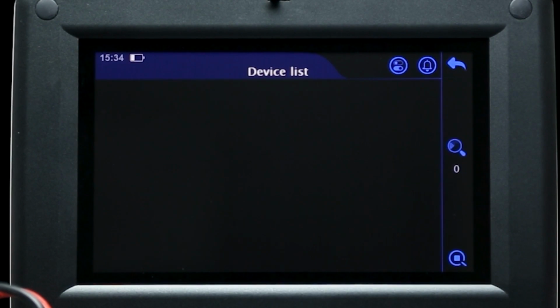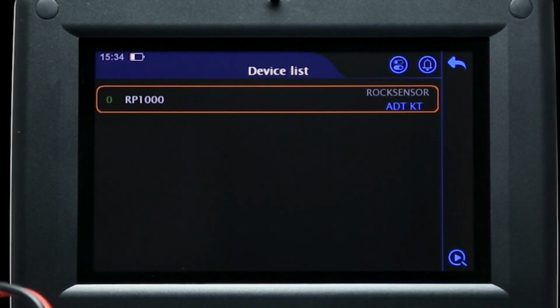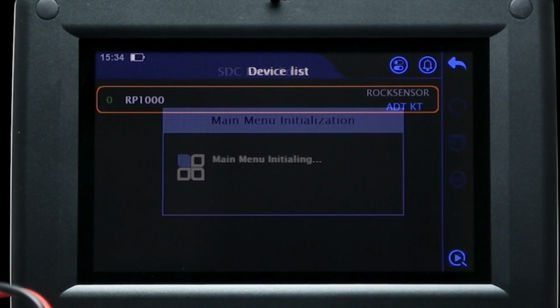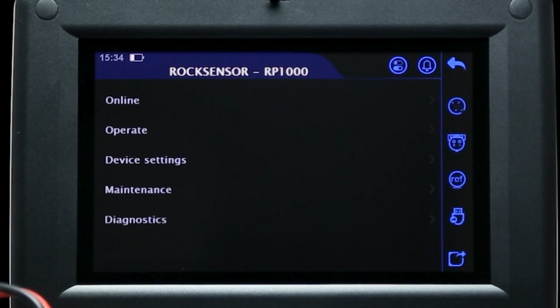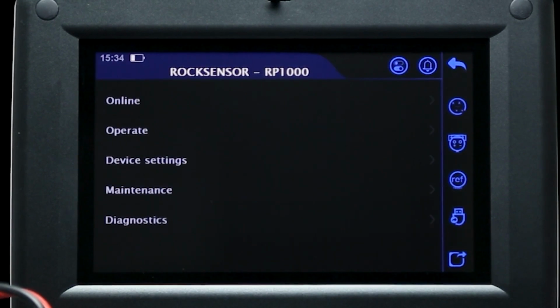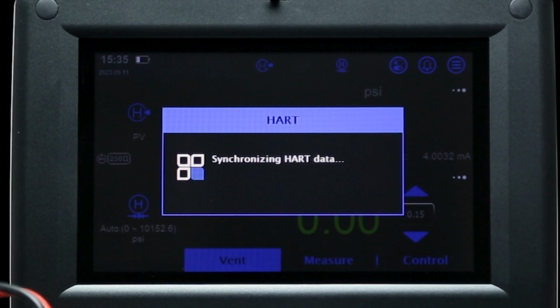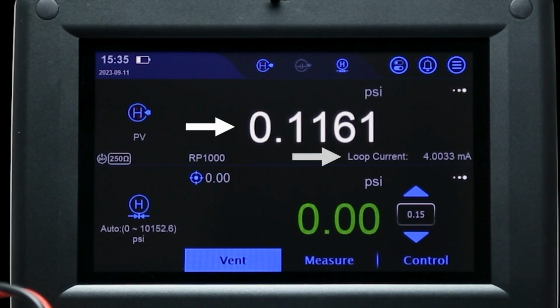Once the device has been connected correctly, the transmitter should turn on and appear in the HART device list. After selecting the transmitter, you'll have access to the full range of settings that are provided by your HART selected device. Once you have finished configuring the device, press the back button to return to the home screen, where you can see that the transmitter pressure, loop current, and 762 pressure are shown.